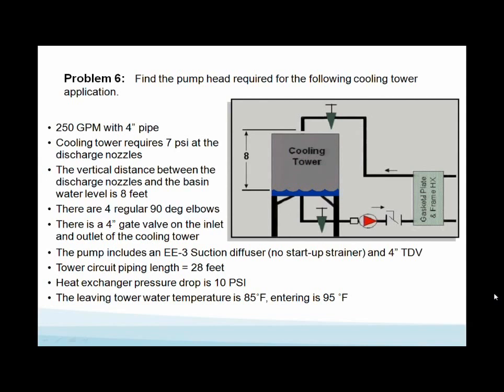Now, I want you to do a detailed pump head loss calculation. If you're bored with this, I'm sorry. The code's going to make you do this. That's the message I'm trying to give you. You've got to start doing this. We haven't been taking this much time and picking the pump for the critical circuits. We have to now. By code, you're going to have to do this and put it in your file. It's that critical because of the energy involved in running a pump. And we want to make sure we do the right estimate.